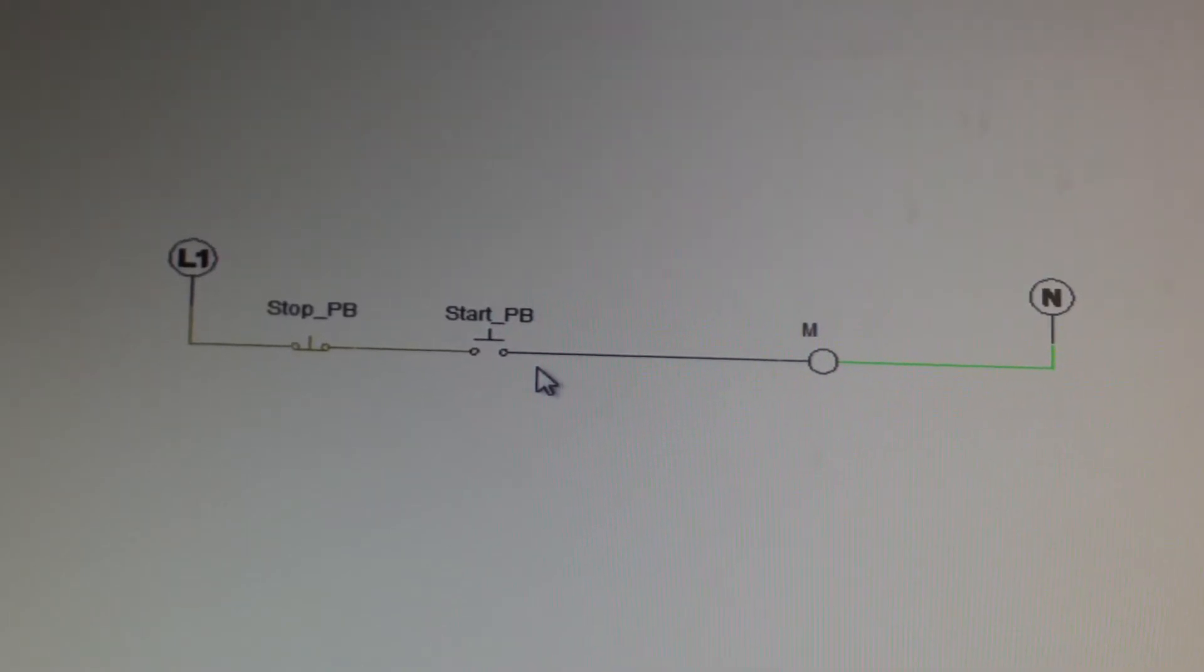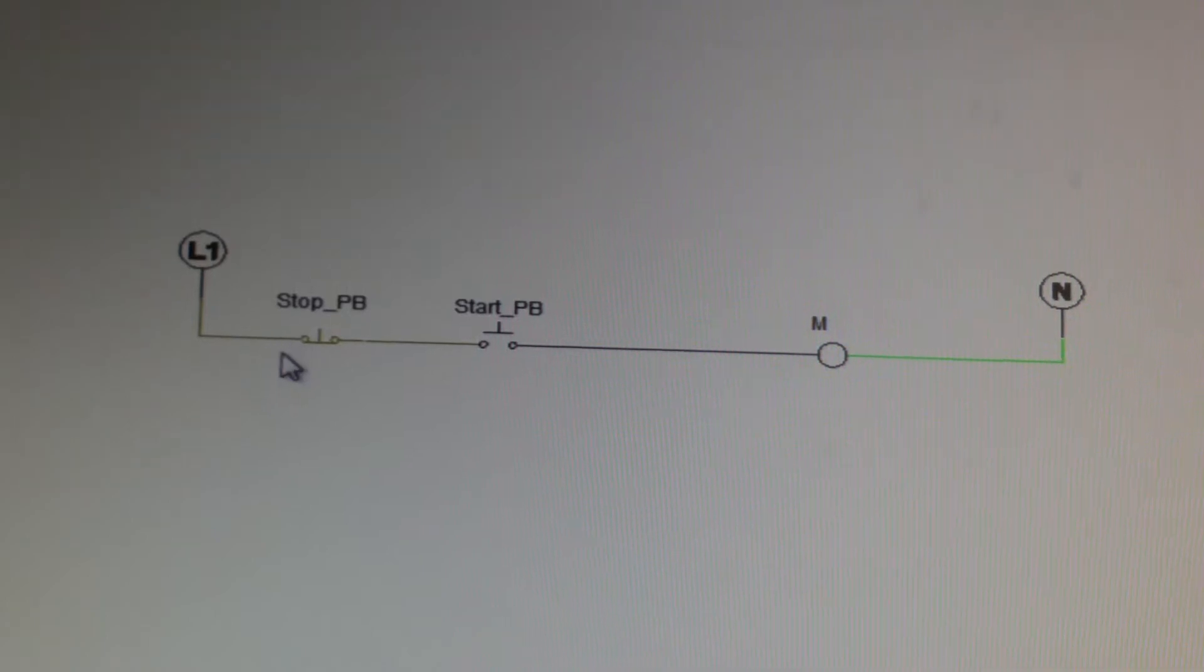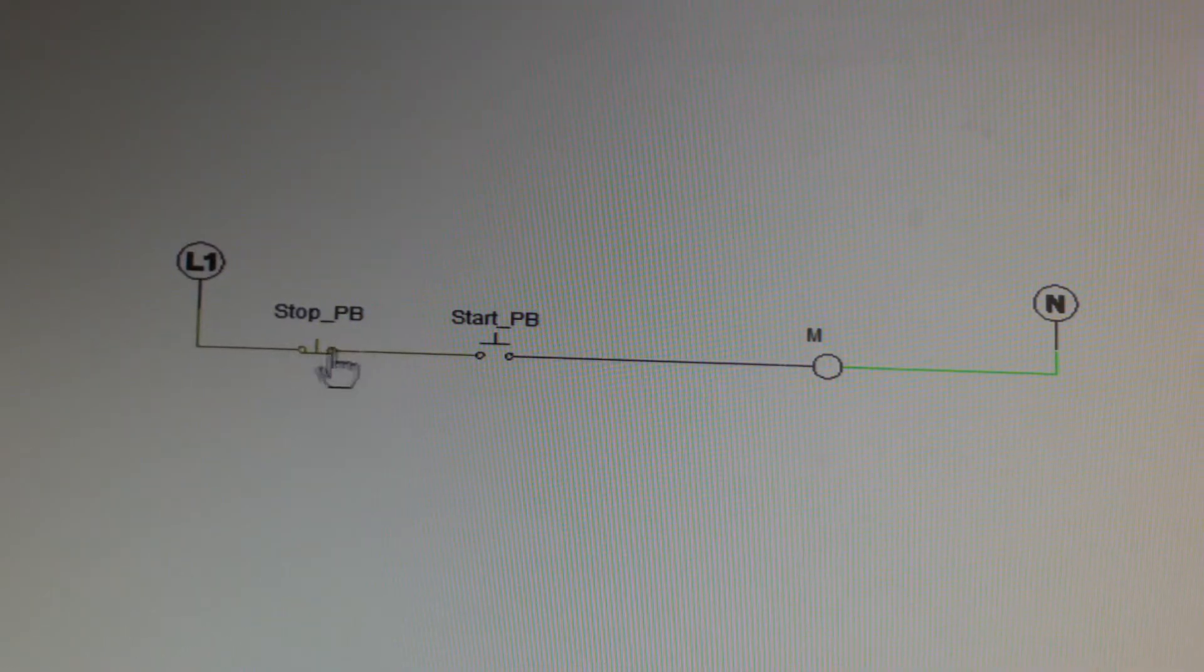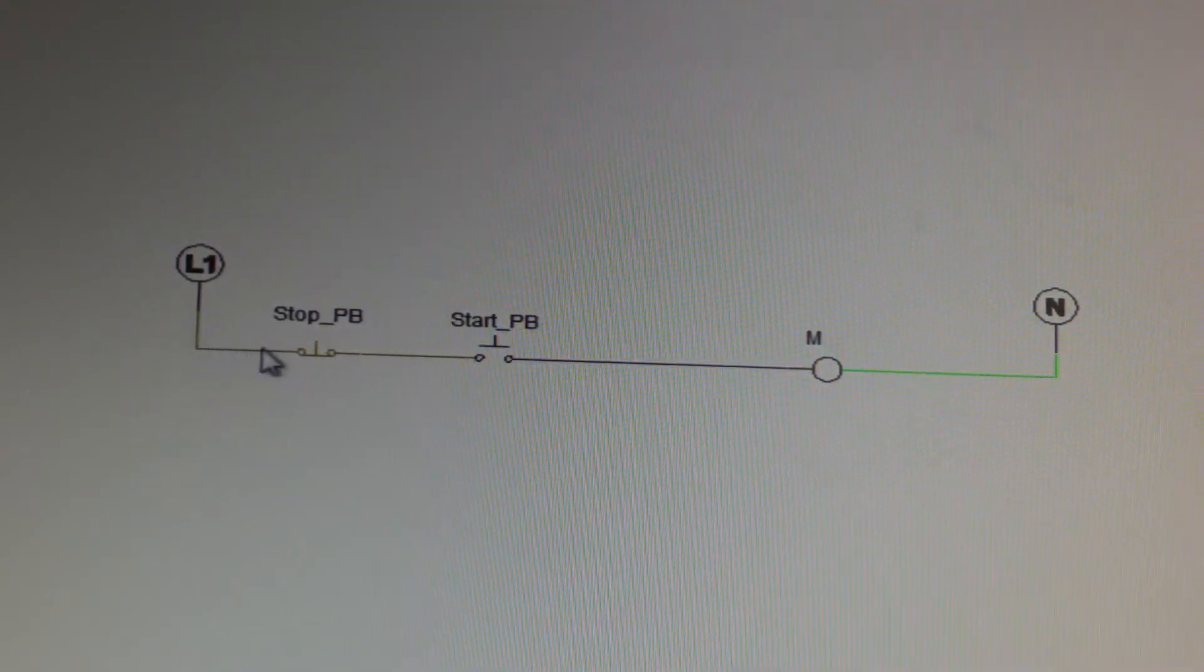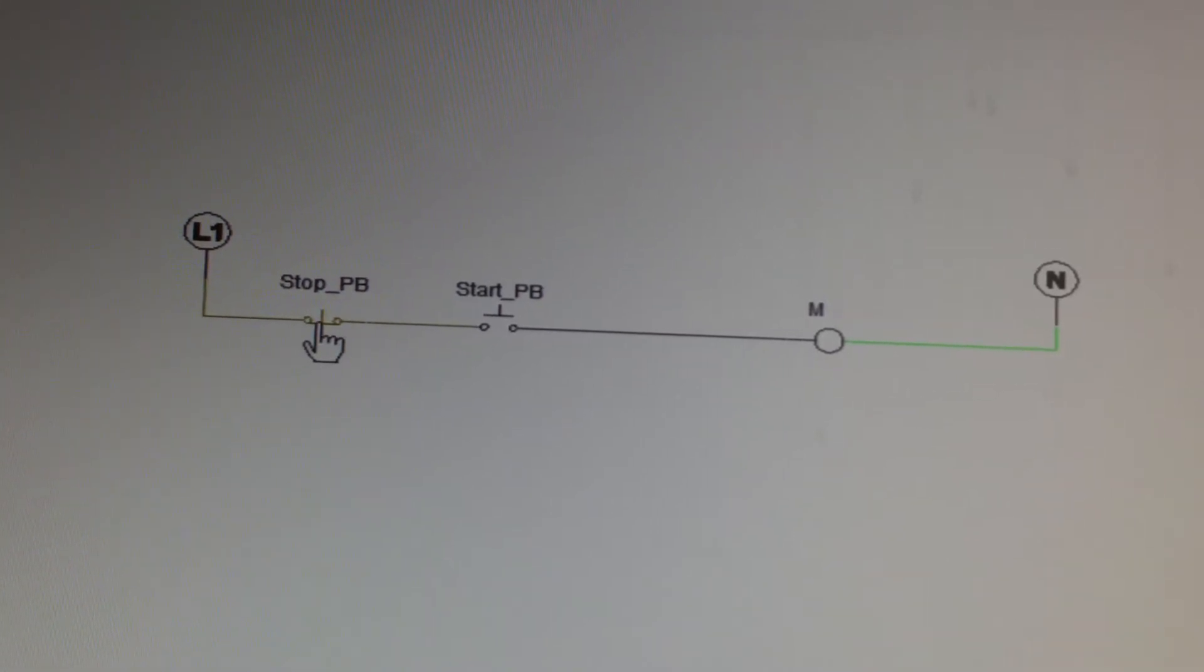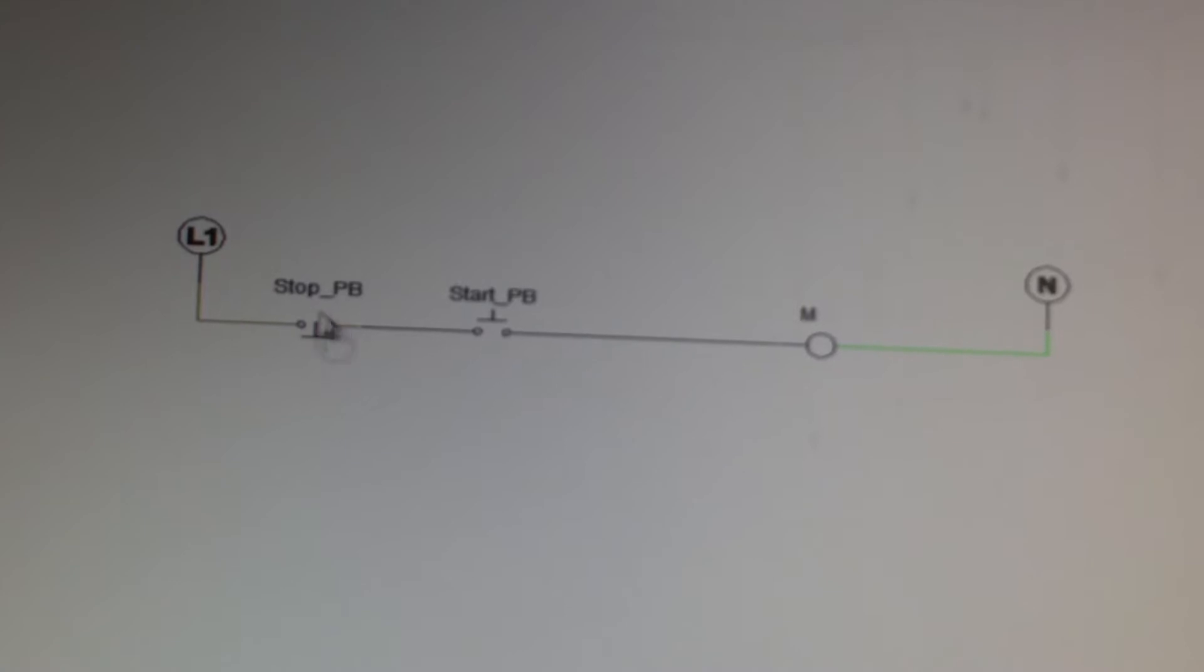So I say stop PB, that means stop push button. When the push button is not pushed, it is allowing continuity. So if this L1 is 120 volts, it's going to allow 120 volts through here without pushing it. But as soon as I push it, it's going to open it.